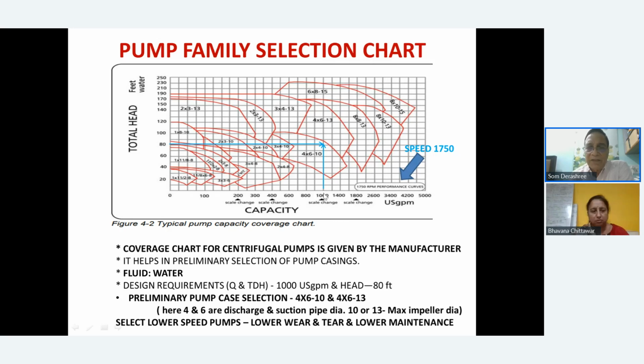So let's say you needed US GPM as 1,000, and you have a requirement of about 80 feet as the head. Then you find here that you are falling within 4-6-10. Now, what is this 4-6-10? But of course, if you remove this curve, you will also find that even 4-6-13 also is equally close to this. So there are two actually primary selections, 4-6-13 and 4-6-10.